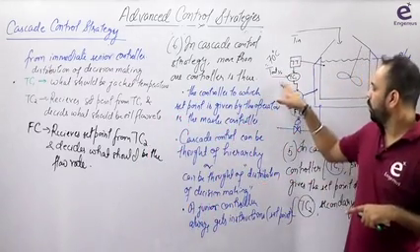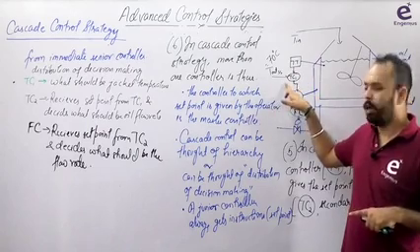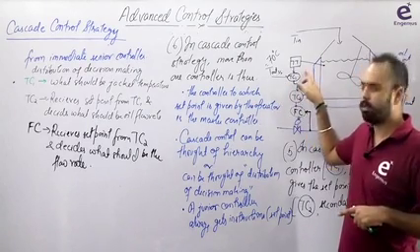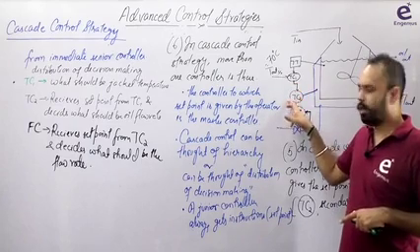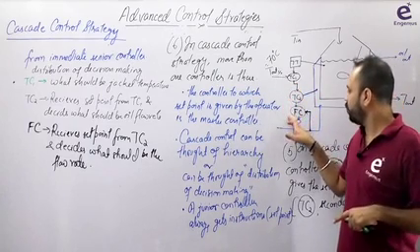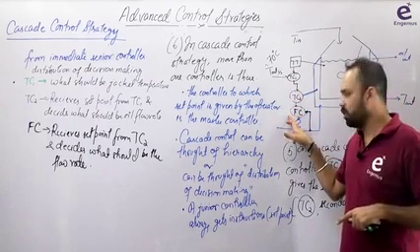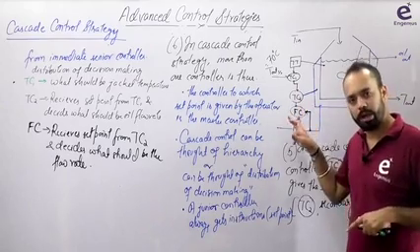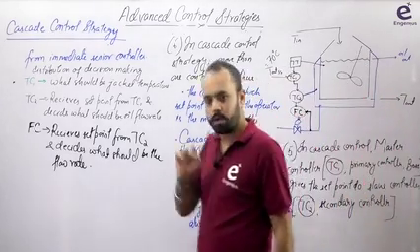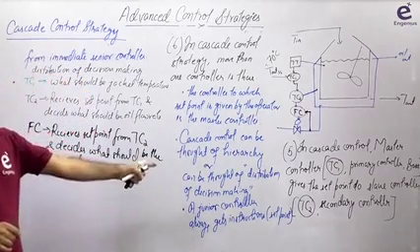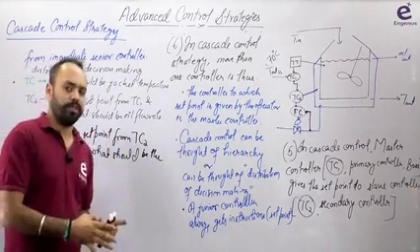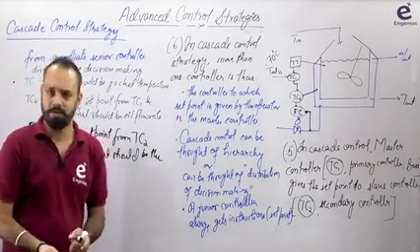So here also see the primary controller, one set point provided by the user, one measurement, right? Secondary controller TC2, set point is given by TC1, then measuring the jacket temperature. FC, set point is given by TC2 and measuring the flow rate. करेक्ट. सो हर एक कंट्रोलर को एक सेट पॉइंट चाहिए होता है, एक मेजरमेंट चाहिए होता है. This is the meaning of distribution of decision making. Whenever distribution of decision making is there, the result is always perfect.